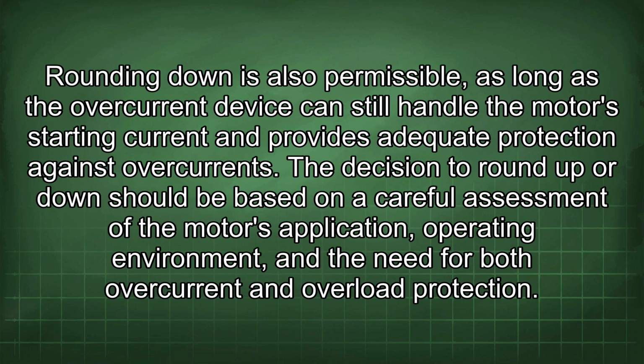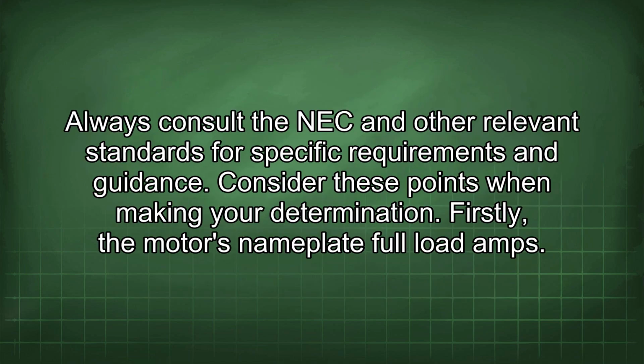Rounding down is also permissible, as long as the overcurrent device can still handle the motor's starting current and provides adequate protection against overcurrents. The decision to round up or down should be based on a careful assessment of the motor's application, operating environment, and the need for both overcurrent and overload protection. Always consult the NEC and other relevant standards for specific requirements and guidance. Consider these points when making your determination.